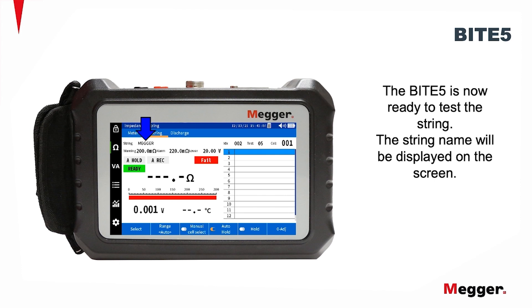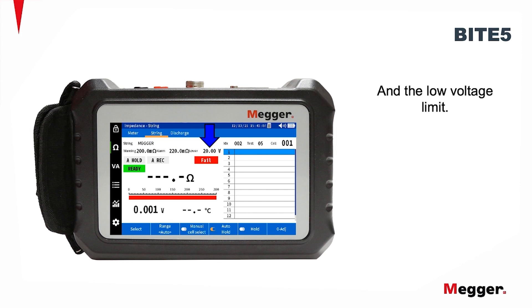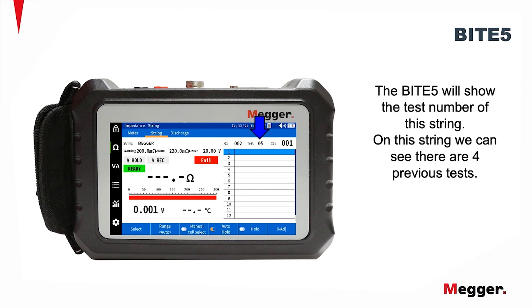The string name will be displayed on the screen, along with the impedance warning limit, the impedance alarm limit, and the low voltage limit. The BITE5 will show the test number of the string. On this particular string, we can see that there are four previous tests.